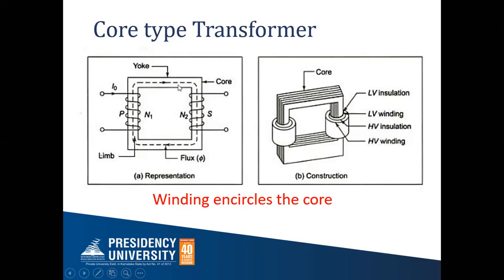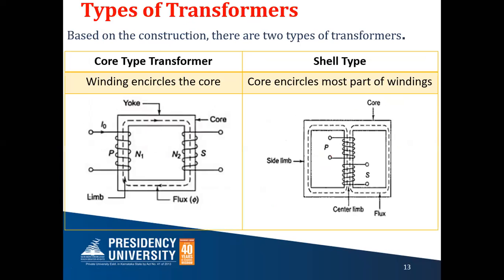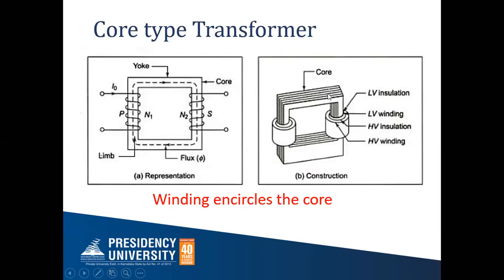But even though, the core will have some kind of current, because we are trying to reduce the conduction by making the core into laminations. See here, sheets, a number of laminations. Each sheet is separated by some kind of insulation. So we are trying to make it as poor a conductor as possible, but even so, one sheet will carry some circulating current.